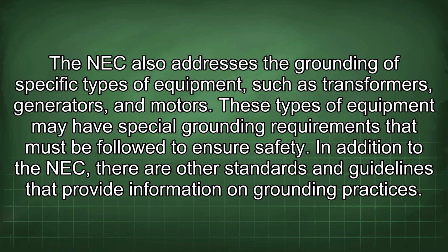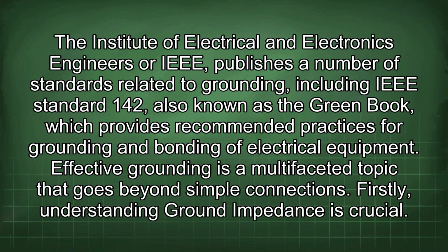The NEC also addresses the grounding of specific types of equipment such as transformers, generators, and motors. These types of equipment may have special grounding requirements that must be followed to ensure safety. In addition to the NEC, there are other standards and guidelines that provide information on grounding practices. The Institute of Electrical and Electronics Engineers, or IEEE, publishes a number of standards related to grounding, including IEEE Standard 142, also known as the Green Book, which provides recommended practices for grounding and bonding of electrical equipment.